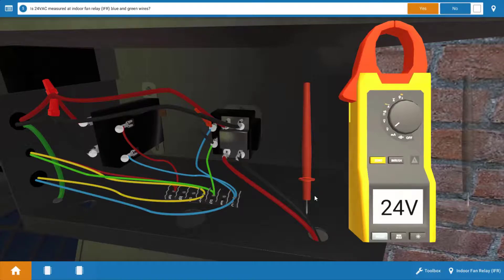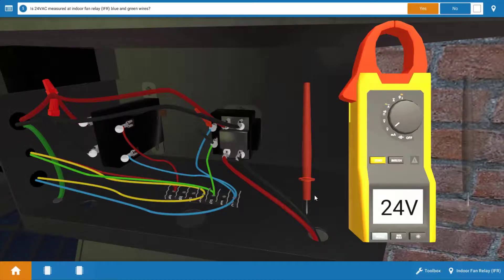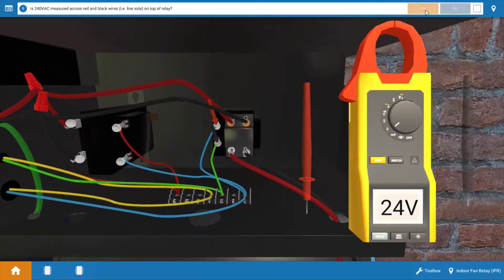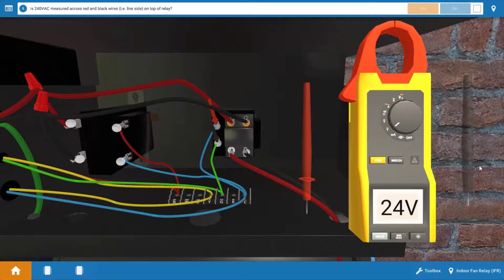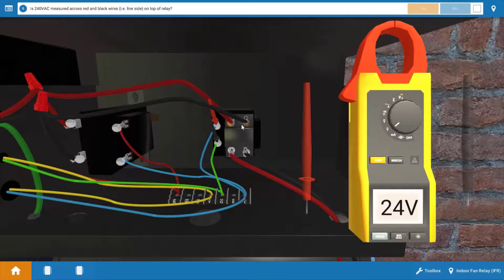So this verifies that the thermostat's OK. The fan switch is functioning properly and it's sending 24 volts to the relay coil. We're going to click yes on the procedure guide that we've measured 24 volts. And now we're going to check for the line side voltage. In other words, we're going to verify that we have 240 volts coming into the relay at the top here.